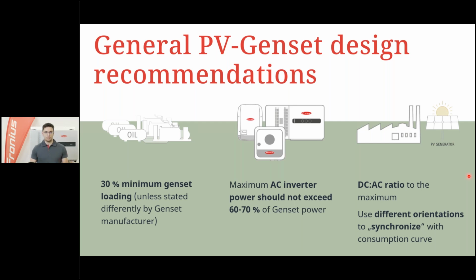The second point is in combination with the first point: the maximum AC inverter power should not exceed 60 to 70% of the genset power in order to not regulate down unnecessarily. So this means, I give you an example, if we talk about a 500 kVA genset, we must not have more than 70% of this inverter power.